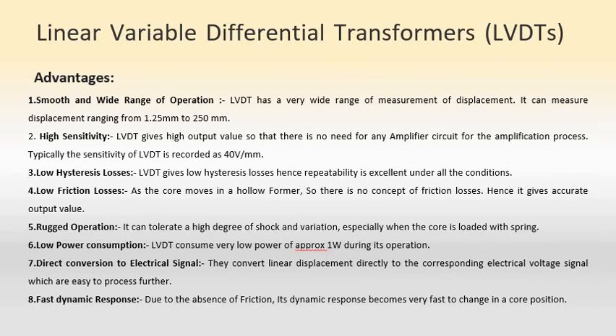LVDT gives a high output value, so there is no need for any amplifier circuit for the amplification process. Typically the sensitivity of LVDT is recorded as 40 volt per millimeter, and it has low hysteresis losses and low friction loss also. And because LVDT has low hysteresis losses, repeatability is excellent. The repeatability of an LVDT is good under all conditions. And friction losses are also less in the case of LVDT.